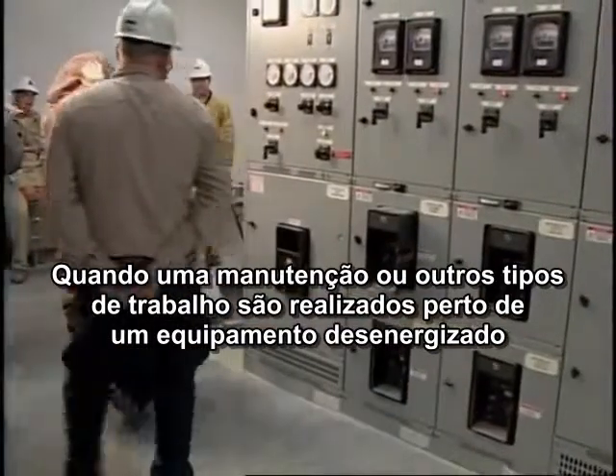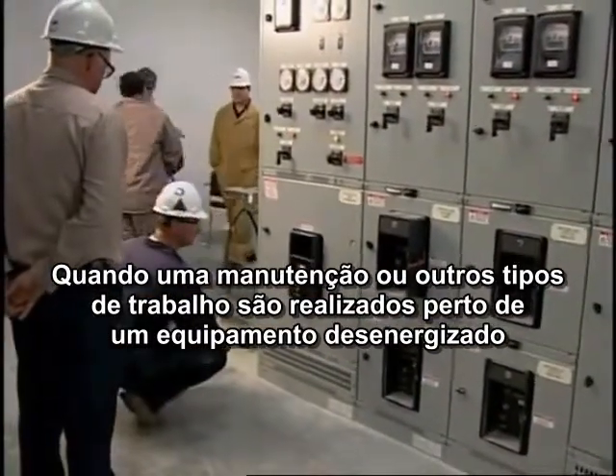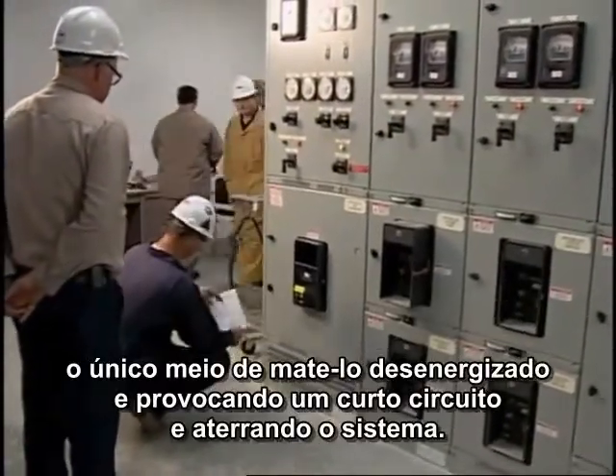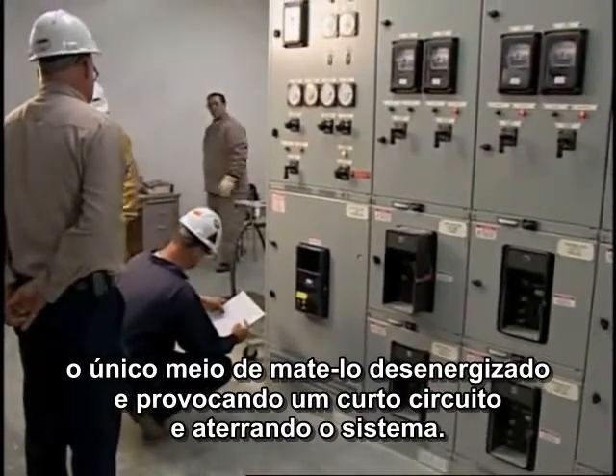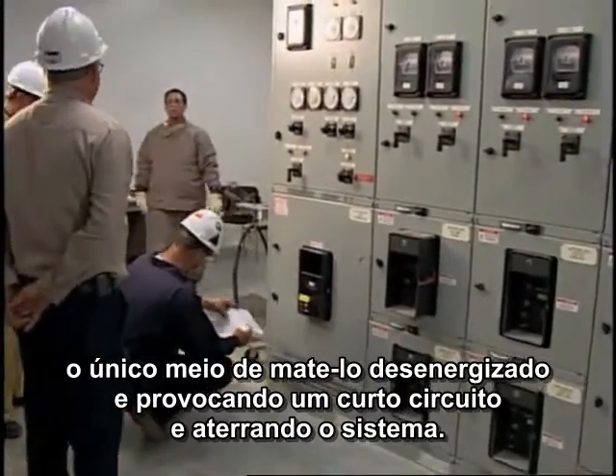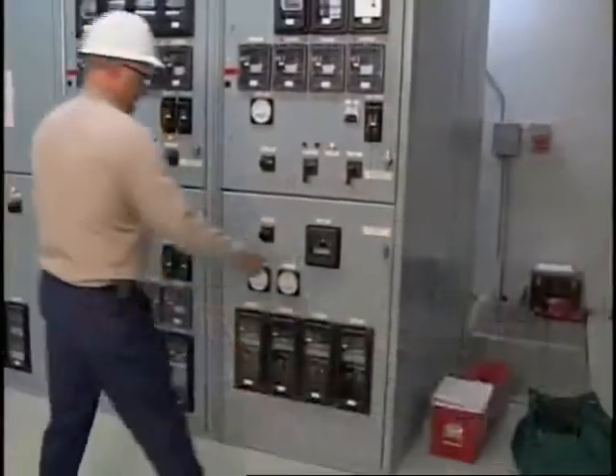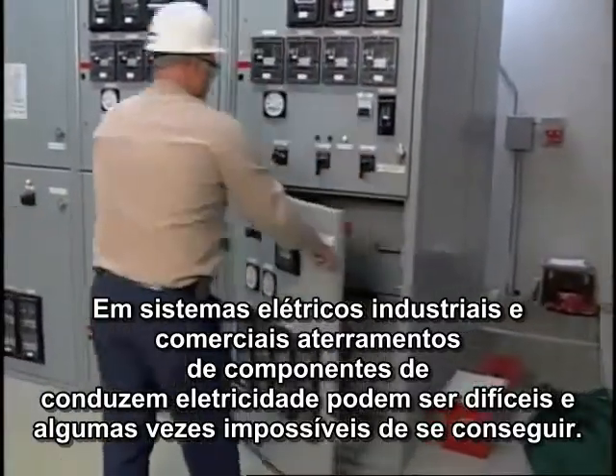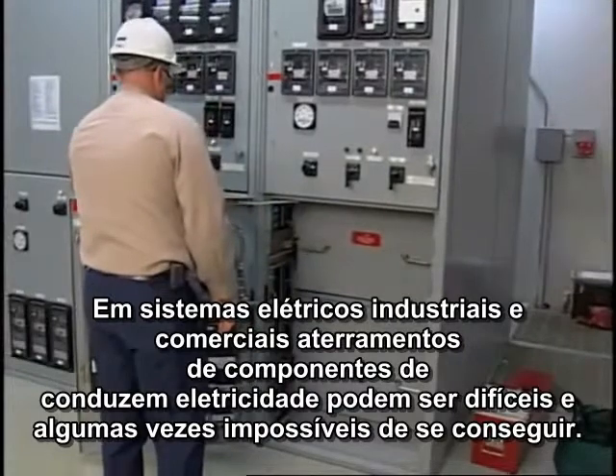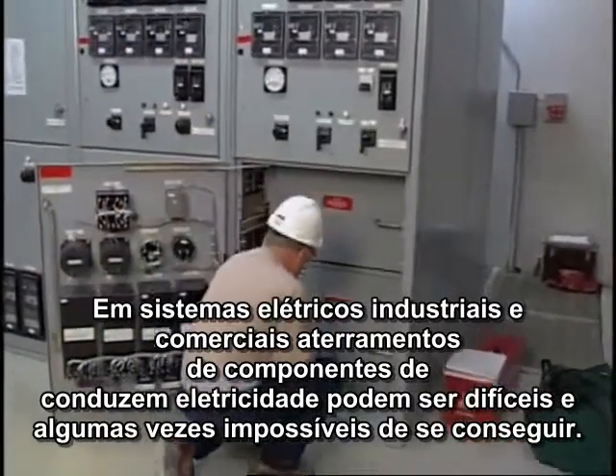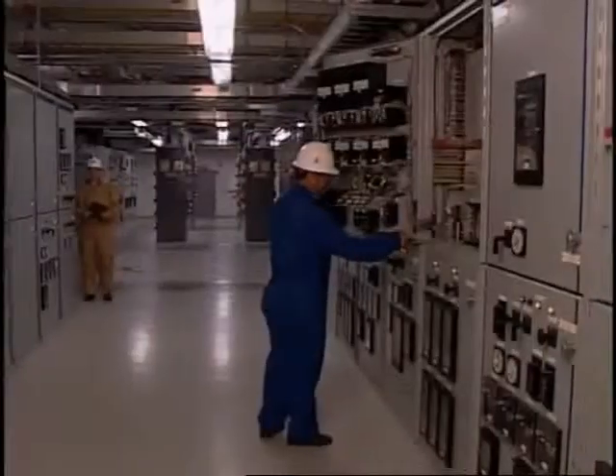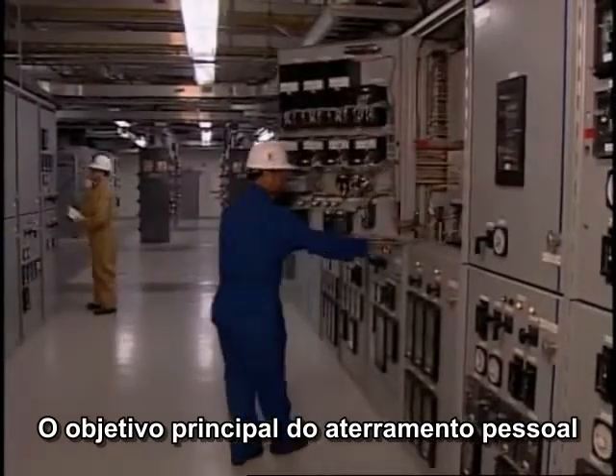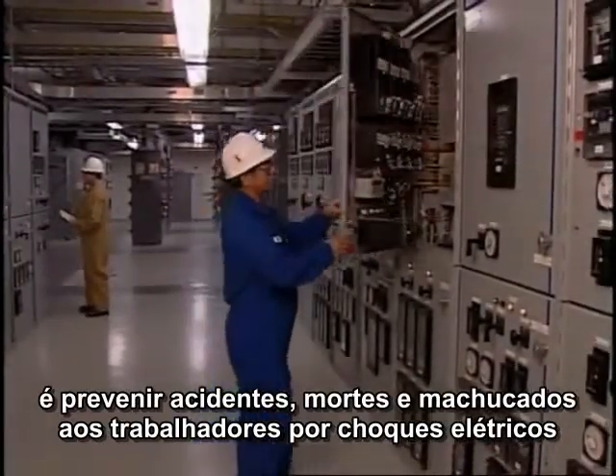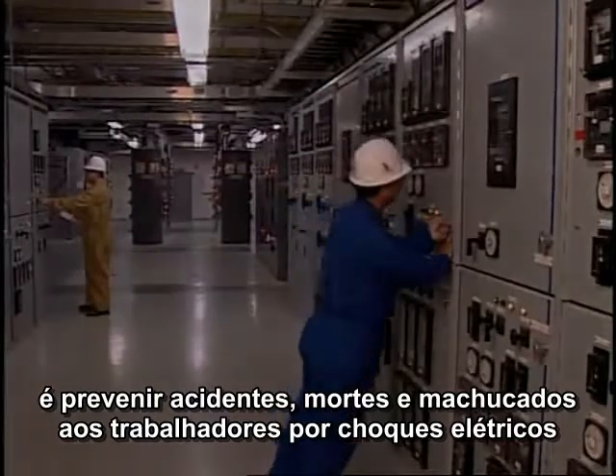When maintenance or other type of work is performed on or near de-energized equipment, the only way to assure that the equipment will remain de-energized is to short circuit and ground the system. In industrial and commercial electrical systems, grounding of current-carrying components can be difficult and sometimes impossible to do. The primary purpose of personal protective grounding is to prevent accidental death or injury to workers from electric shock by minimizing the magnitude and duration of the hazard.